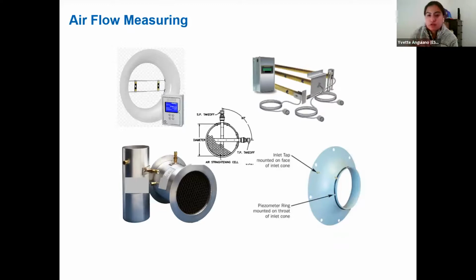So next I want to touch on airflow measuring devices. I'm going to highlight two major types: thermal dispersion airflow measuring, and differential pressure. Just giving a rundown of the examples provided here, we've got the thermal dispersion types up top. We've got a pitot tube kind of layout here, and then this bottom right is a piezometer ring airflow measuring device. So these two you'd be using as thermal dispersion, and then these bottom ones would be using differential pressure. But we'll get into what those mean next.